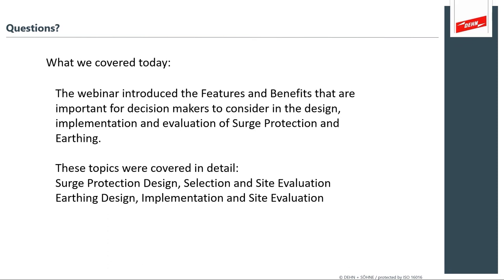In normal maintenance cycles, it's probably once a year is sufficient to go through and look at your SPDs. But again, they don't necessarily last forever. So sometimes I hear things like, well, every 10 years, you might want to replace your SPD. And that might work for somebody in a modest climate. If you're in southern Florida where I'm at, I had heavy thunderstorms just the other day. So I'm paying attention to my surge protection devices every year. So it definitely depends on your level of risk that you're willing to absorb and the type of environment that you're subjected to.